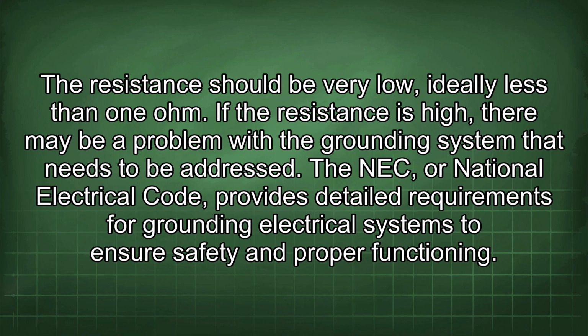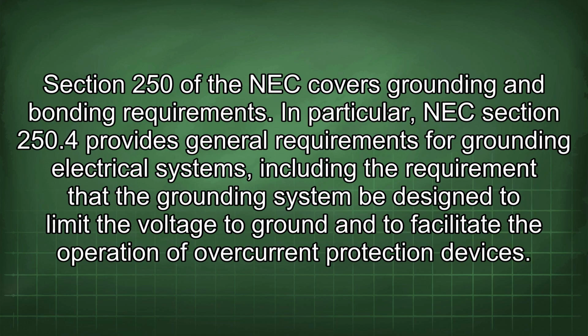The NEC, or National Electrical Code, provides detailed requirements for grounding electrical systems to ensure safety and proper functioning. Section 250 of the NEC covers grounding and bonding requirements. In particular, NEC Section 250.4 provides general requirements for grounding electrical systems, including the requirement that the grounding system be designed to limit the voltage to ground and to facilitate the operation of overcurrent protection devices.